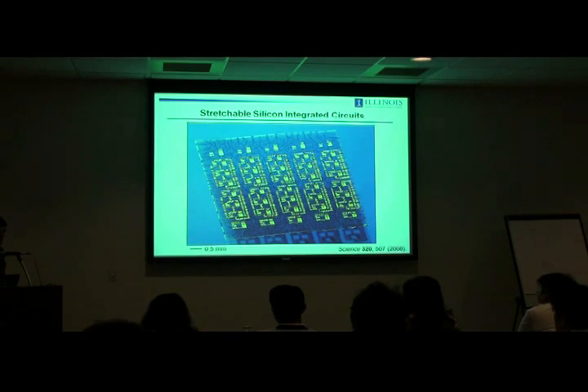Yeah, so that's a good question. So we have mechanical fatigue testing setups that allow us to cycle these devices back and forth. So in an aggressive test, we'll run up to maybe 100,000 stretching cycles up to some predefined strain level. We also do bending fatigue as well. So I think at an academic level, that's pretty good. For a real commercial product, you may want to go even a little bit beyond that.